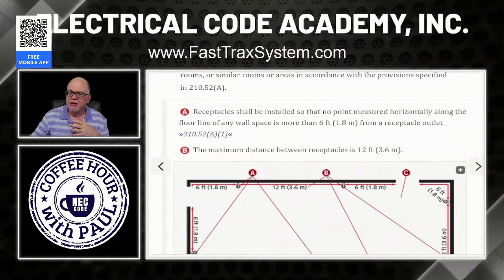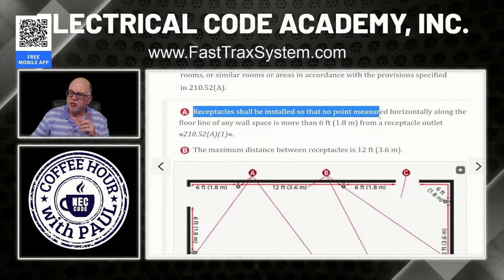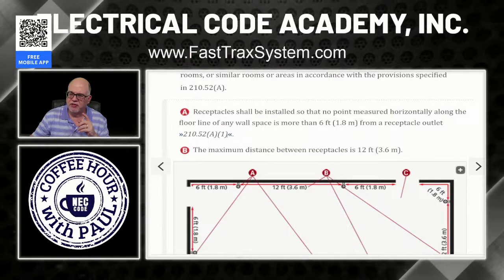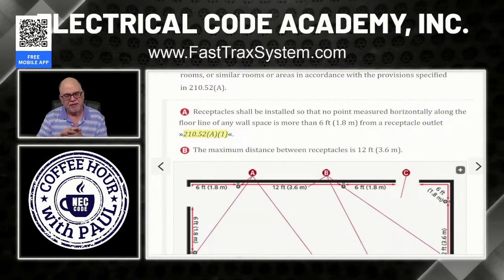So what does it say? It says receptacles shall be installed so that no point measured horizontally along the floor line of any wall space is more than 6 feet from a receptacle outlet. That's what it says in 210.52(A)(1). It's a great time to pause and read what that says in the code.